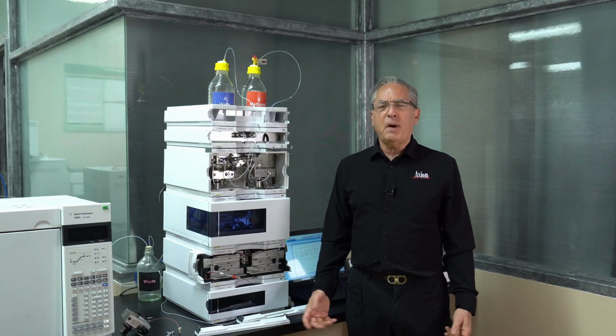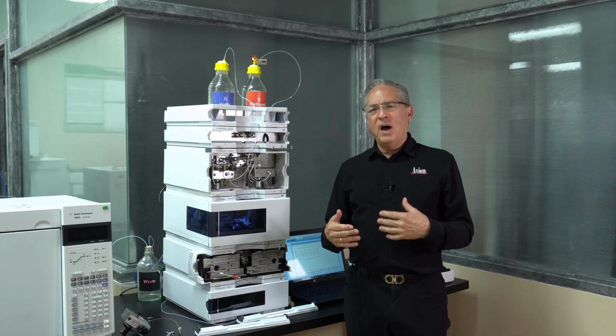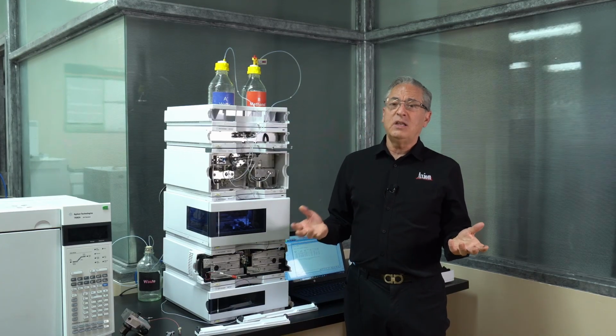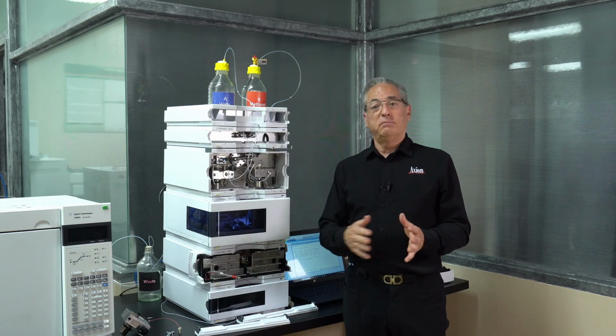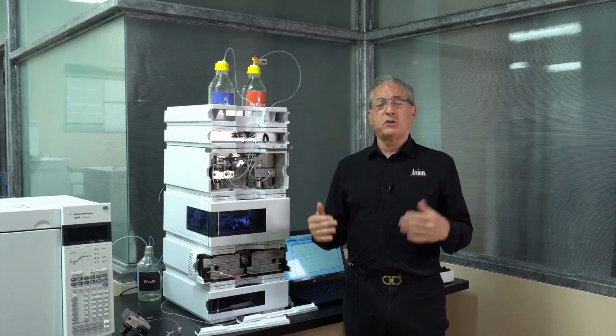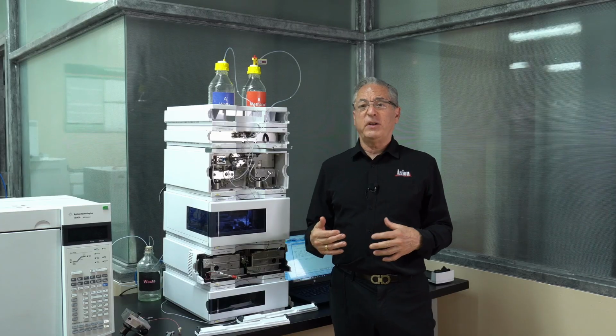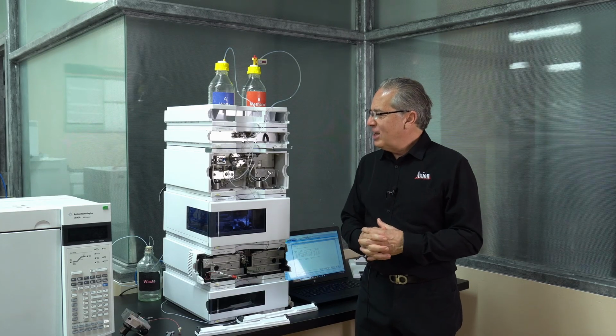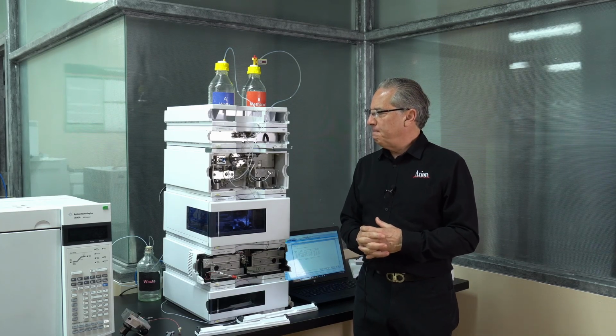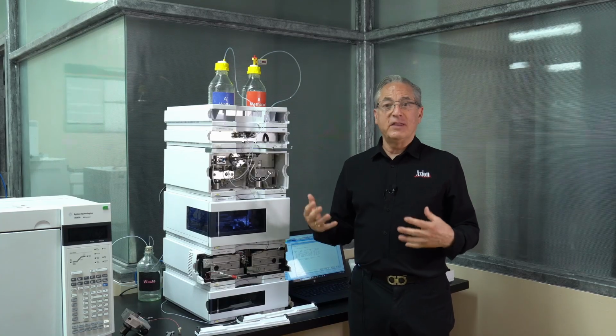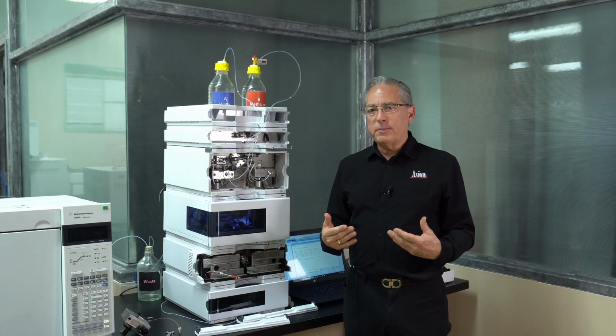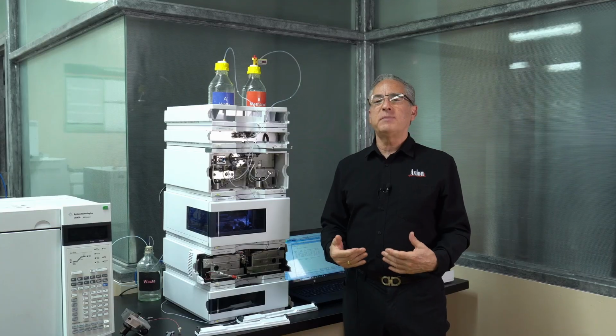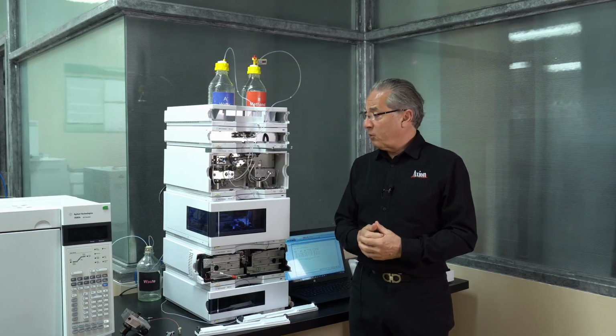That's important because if pump seals wear out, if they break during a run, then if you're a pharmaceutical company especially, then you have to repeat all the results. You get a bunch of blank chromatograms, and you got to write a big story, big letter to the FDA explaining why you're throwing away all that data. So we generally don't like to operate when the system is broken. So we change the pump seals, preventative maintenance. We change them every 6 months so they never wear out.